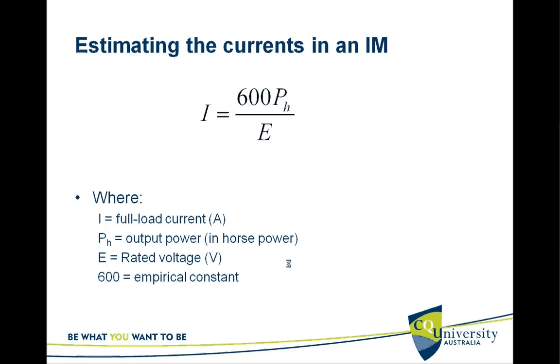The full load current I can be found as 600 × Ph / E, where Ph is the output power in horsepower, E is the rated voltage, and 600 is an empirical constant.